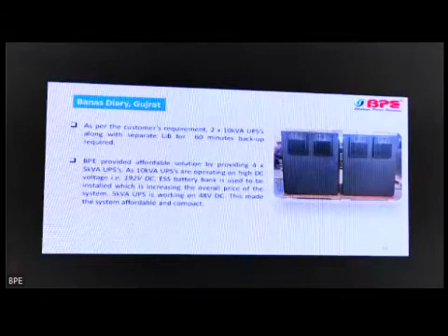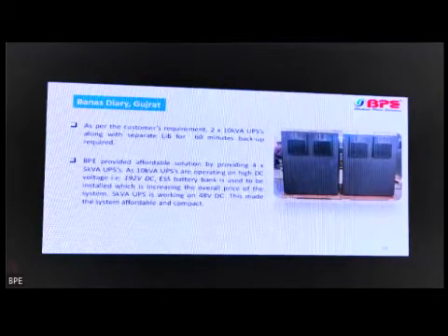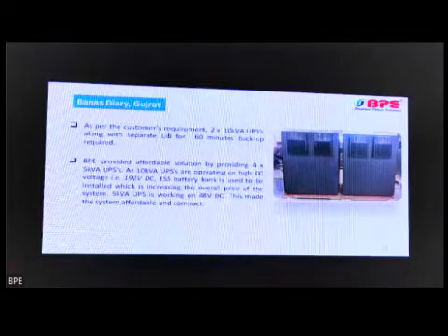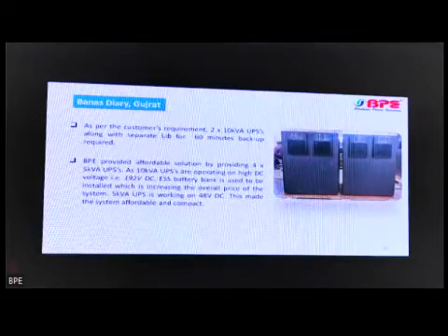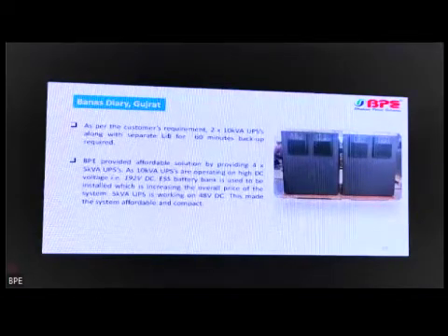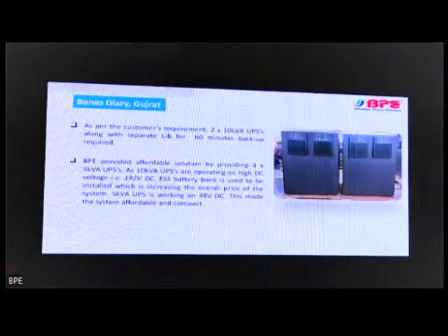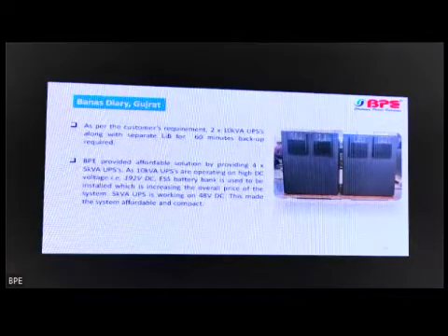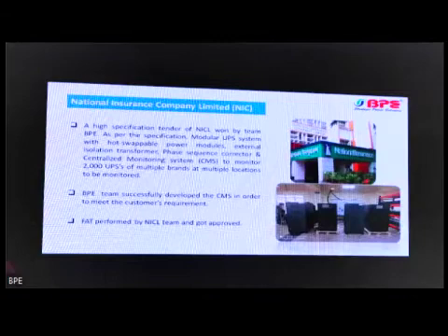Then we have Banas Dairy, Gujarat. As per the customer's requirement, 2 into 10 kVA UPS along with a separate LIB for 60 minutes backup was required. So we provided them 4 into 5 kVA UPSs instead of 2 into 10 kVA UPSs, because the DC bus voltage of the 5 kVA UPS was 48 volt and the 10 kVA UPS was 192 volt. Because of the 48 volt DC bus, the lithium ion battery requirement was lower, and we provided them a very affordable solution.